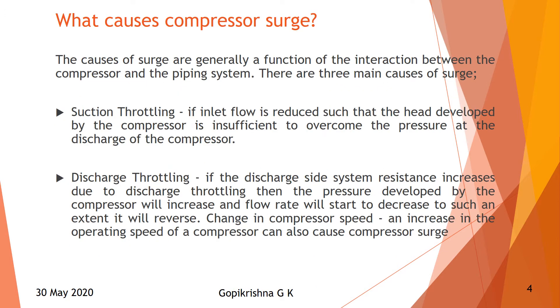The causes of surge are generally a function of interaction between the compressor and the piping system. There are three main causes of surge. First is suction throttle — if the inlet flow is reduced such that the head developed by the compressor is insufficient to overcome the pressure at the discharge side. Second is discharge throttling — if the discharge side system resistance increases due to discharge throttling, then the pressure developed by the compressor will increase and the flow rate will start to decrease to such an extent that it will reverse.